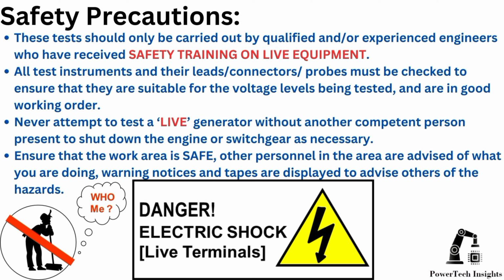All test instruments and their leads, connectors, and probes must be checked to ensure that they are suitable for the voltage levels being tested and are in good working order. Never attempt to test a live generator without another competent person present to shut down the engine or switchgear as necessary. Ensure that the work area is safe. Other personnel in the area are advised of what you are doing. Warning notices and tapes are displayed to advise others of the hazards.